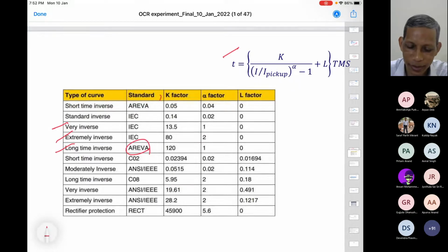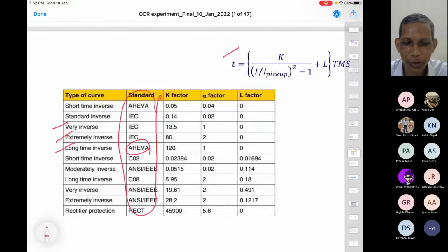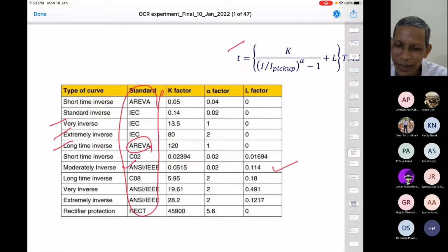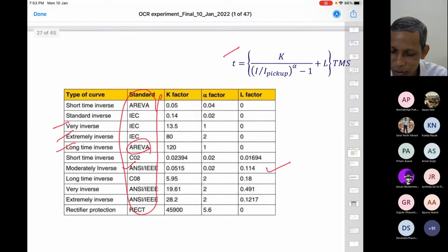What I would like to say is that these are against different standards, and manufacturers have their own standards, so we use one here in our discussion. If you go to the relay, all things are available. You can pick up this or that. But what is being done is that the corresponding distribution agency goes by one. Otherwise, it will be too complex, and it will be troublesome from a diagnostics perspective. So in our analysis, we will confine ourselves to the IEEE perspective, but there are other standards too, not limited to this one. Each manufacturer has their own curves as well.